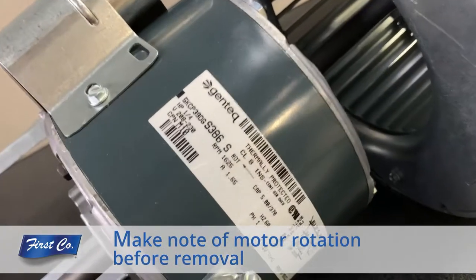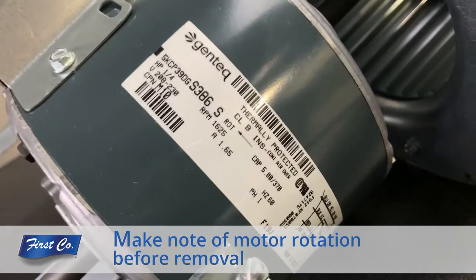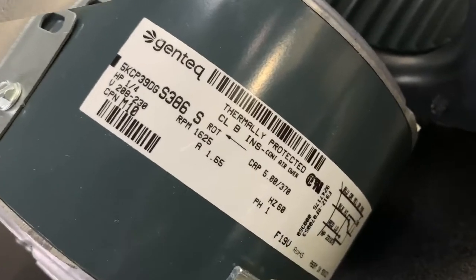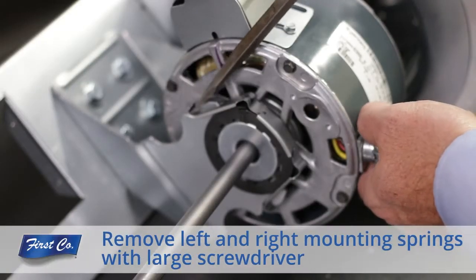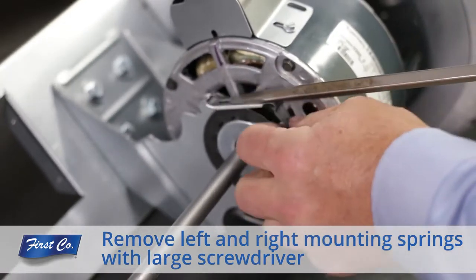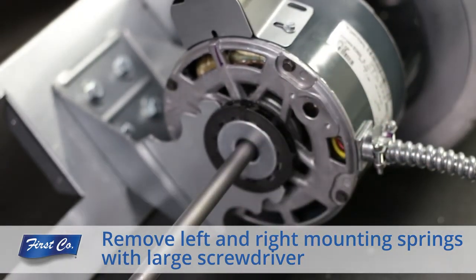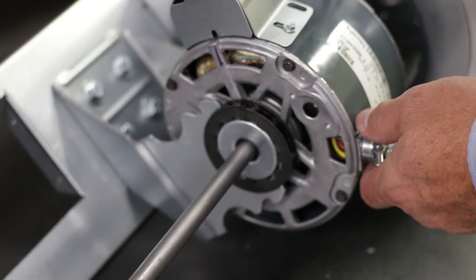Make note of the direction of the motor rotation before removing the motor. There will be a diagram on the motor itself. Using a large flat tip screwdriver, remove the mounting springs. Be sure to remove the spring clips on both sides of the motor.